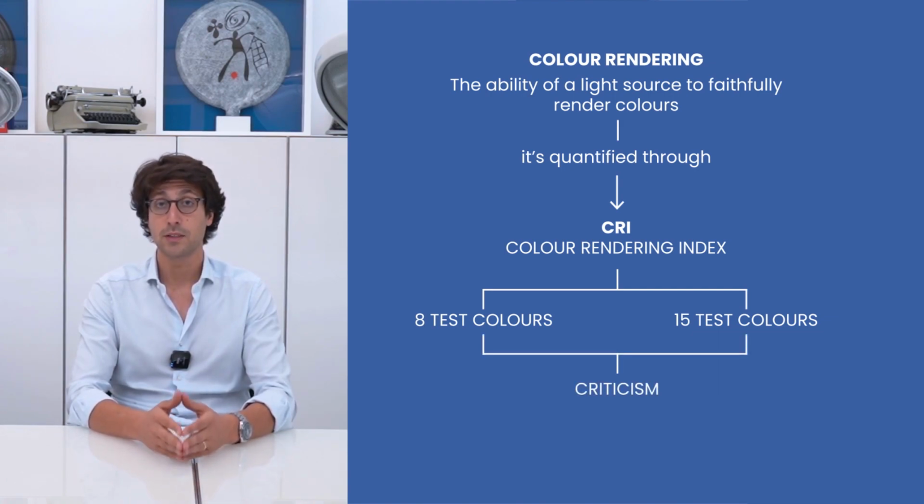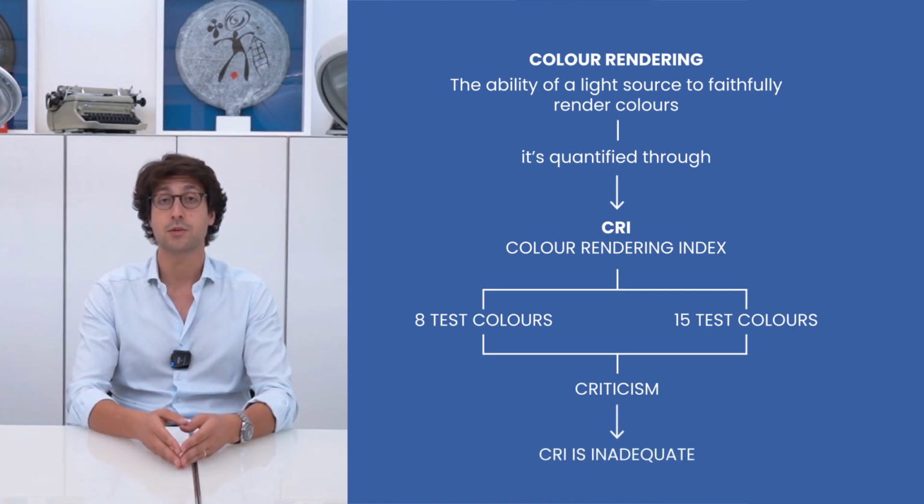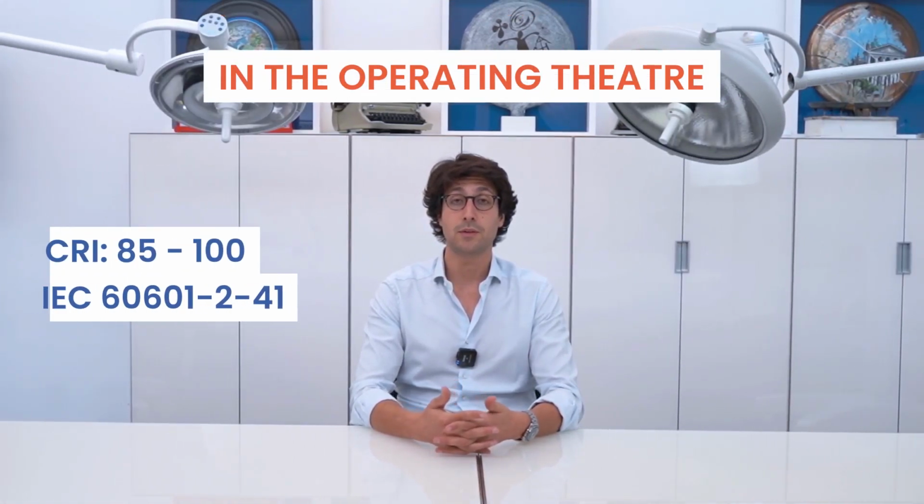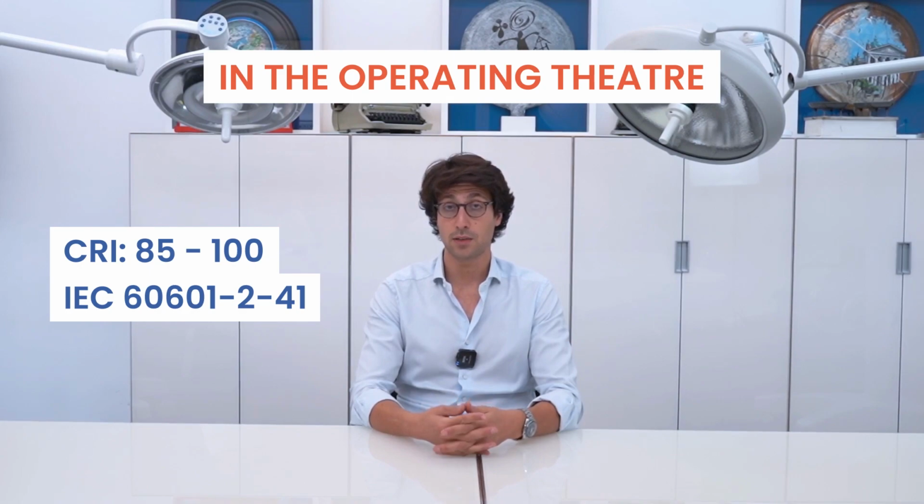However, both of these methods have faced significant criticism due to their inability to truly represent color rendering. Taking this into account, we then examined the normative requirements for color rendering in the context of an operating room. Expanding on this idea, we conducted a thorough assessment of potential future advancements. One such advancement could involve substituting the request for a specific color rendering index with a specified value of TM-30.